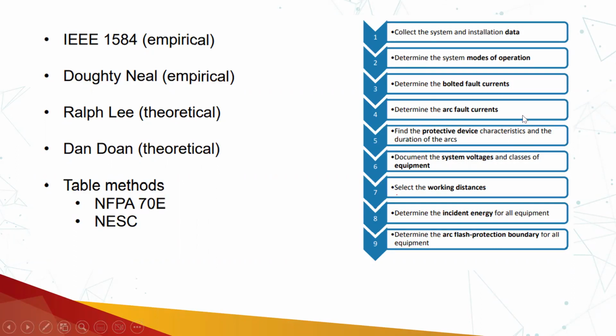So the resistance is there in the arc fault, so the value of the arc fault current is lesser as compared to the bolted fault current. Find the protective device characteristics and the duration of the arc. So device protection we are going to do. Document the system voltage and classes of the equipment. Select the working distance and determine the incident energy for all the equipment.